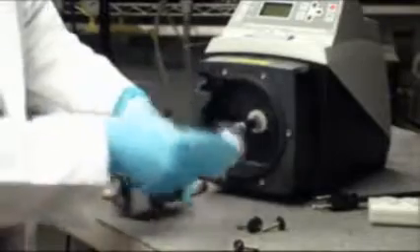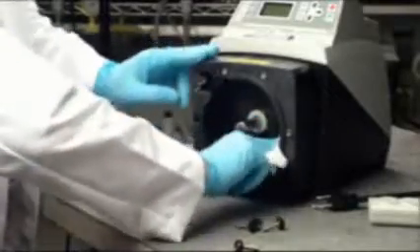The roller assembly and pump head should be inspected and cleaned before installing a new pump tube. This is especially important if the pump tube ruptured and the TFD system was activated. Be sure to also wipe clean the sensor pin with the front side facing forward.